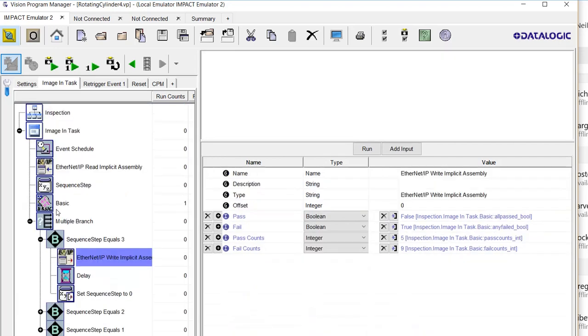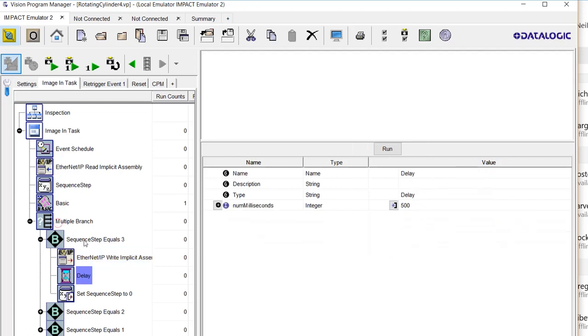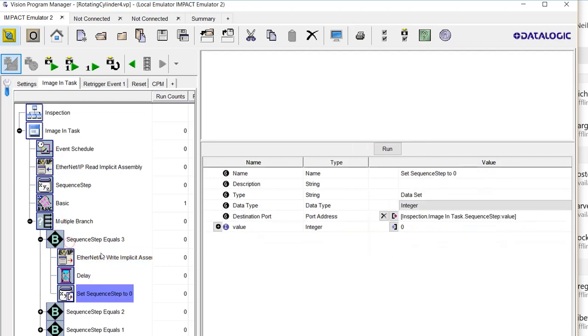Once the PLC commands us to stop by sending a 3, we'll update these bytes in the Ethernet IP assembly. I threw in a delay and we set the sequence step back to 0. So it does nothing until again commanded by the PLC with a value of 1 to be ready to take the next trigger.